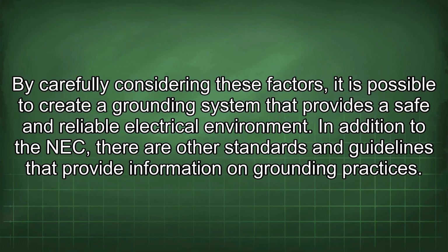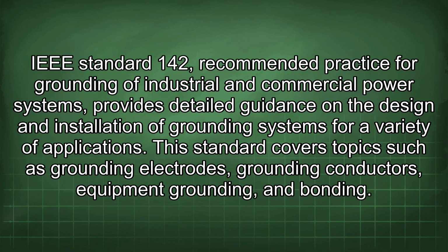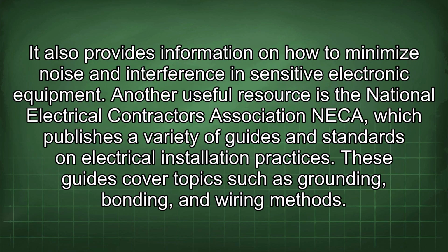In addition to the NEC, there are other standards and guidelines that provide information on grounding practices. IEEE Standard 142, Recommended Practice for Grounding of Industrial and Commercial Power Systems, provides detailed guidance on the design and installation of grounding systems for a variety of applications. This standard covers topics such as grounding electrodes, grounding conductors, equipment grounding, and bonding. It also provides information on how to minimize noise and interference in sensitive electronic equipment.